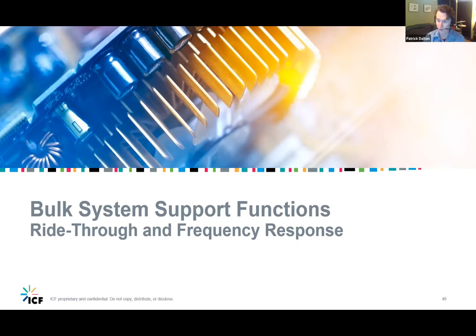So from my perspective, the management setting and the configuration setting in particular is good enough to limit the nameplate value, and the management setting in particular is good enough to limit an export value. I would say that additional relays on top of that are not needed. But I am part of this subgroup of IEEE 1547.2 that is really debating this issue.